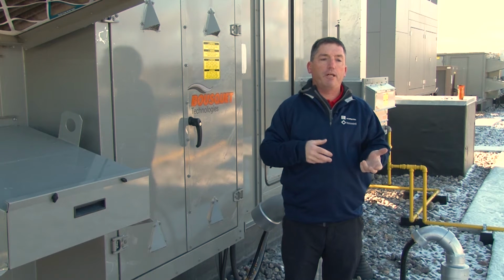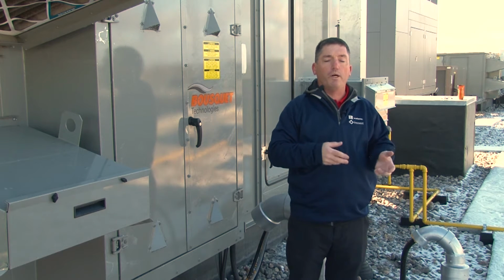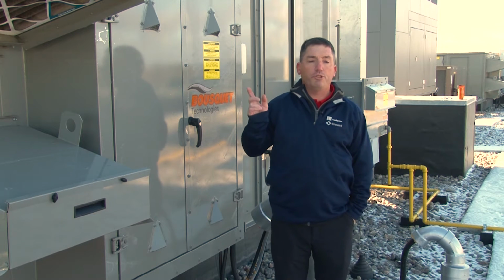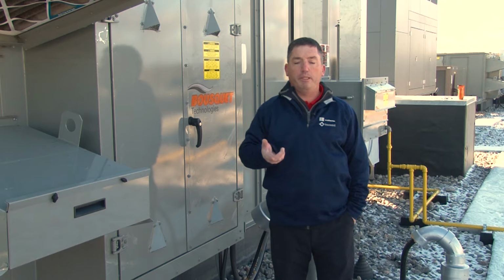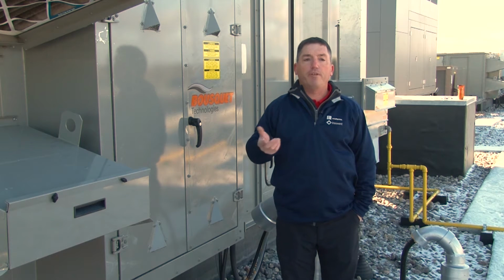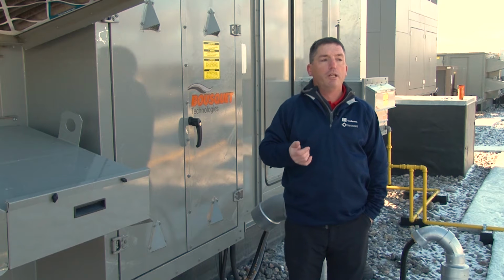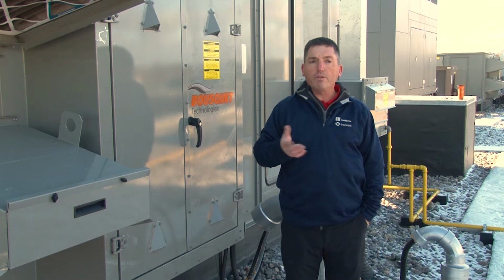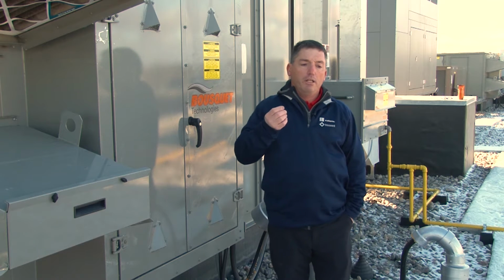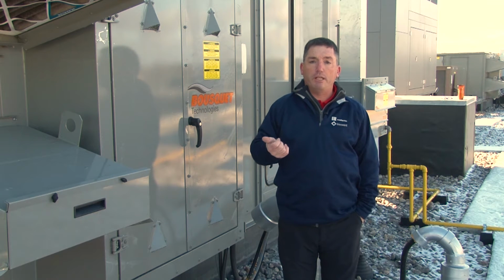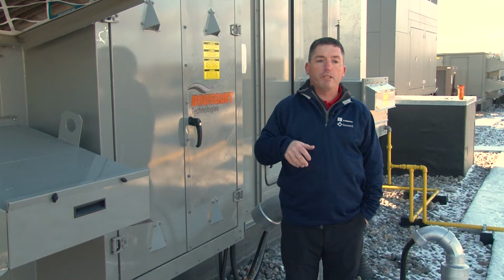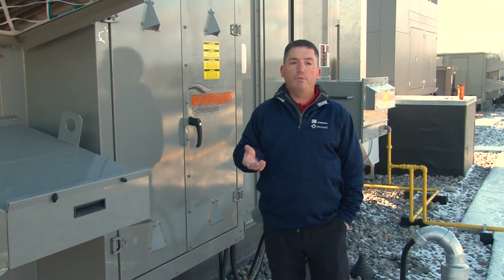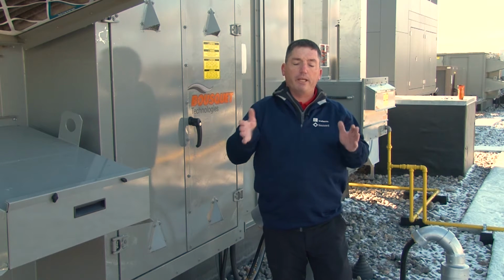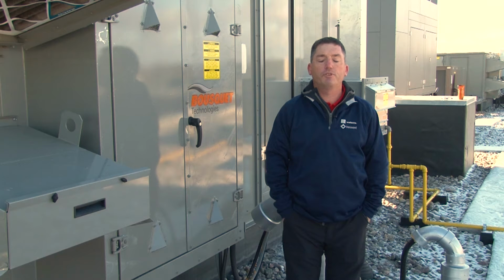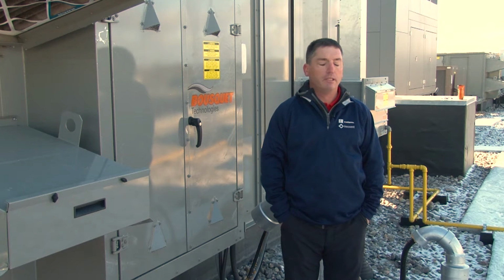When you bring cool outside air in during the winter, it's very dry relative to what you want in the building. So through the 2 larger units, we add humidity so that we can maintain 35 to 40% relative humidity in the space. The reason we want to maintain 35 to 40% is it keeps static electricity down, and it also suppresses viruses that humans are susceptible to. They don't like that range of humidity level to survive, so it helps keep the building healthier.